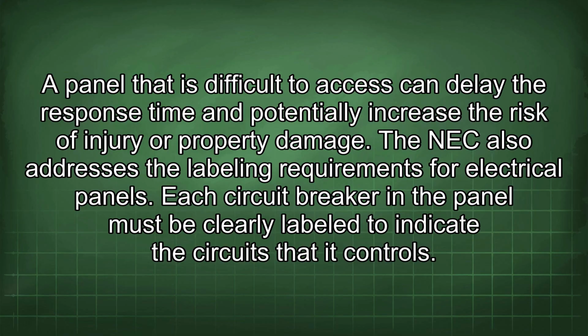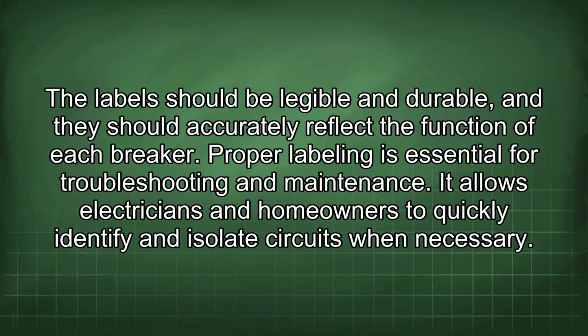property damage. The NEC also addresses the labeling requirements for electrical panels. Each circuit breaker in the panel must be clearly labeled to indicate the circuits that it controls. The labels should be legible and durable, and they should accurately reflect the function of each breaker. Proper labeling is essential for troubleshooting and maintenance. It allows electricians and homeowners to quickly identify and isolate circuits when necessary.